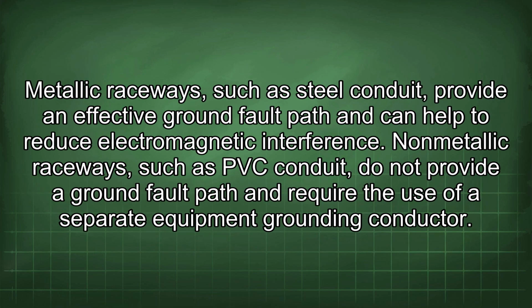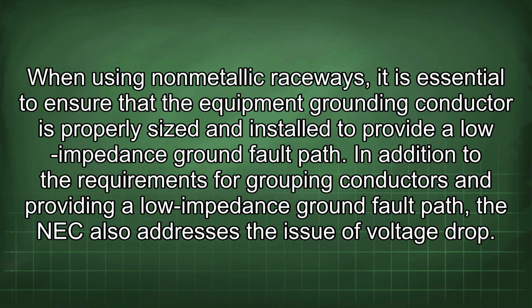Metallic raceways, such as steel conduit, provide an effective ground fault path and can help to reduce electromagnetic interference. Non-metallic raceways, such as PVC conduit, do not provide a ground fault path and require the use of a separate equipment grounding conductor. When using non-metallic raceways, it is essential to ensure that the equipment grounding conductor is properly sized and installed to provide a low impedance ground fault path.